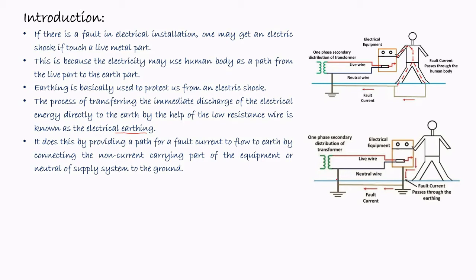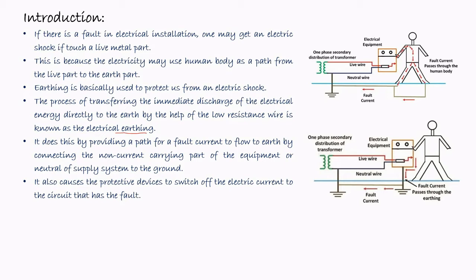As can be seen here, the neutral part of the supply is also grounded, as well as the equipment is also grounded, that means connected to the earth, so that the fault current can directly pass through this grounded wire to the earth. It also causes the protective device to switch off the electric current to the circuit that has the fault. Mostly galvanized iron is used for the earthing purpose. It is a very low resistance material, so it can be used for earthing.